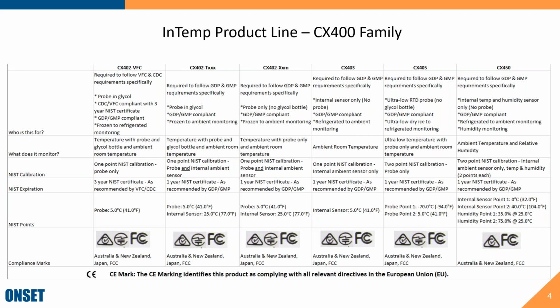Note, this has a 1-point NIST calibration for the probe only. That is a key differentiator, as well as the 3-year NIST certificate. The CX402 are really for GDP and GMP customers. So that's customers following FDA regulations, EU, WHO, USP, all of those different guidelines where they dictate that you really need to have a logger in general.